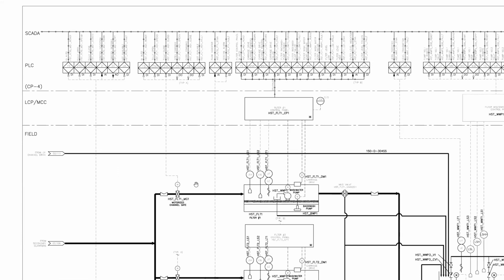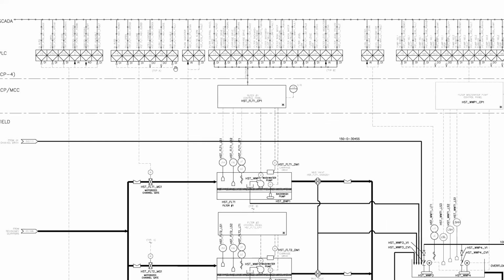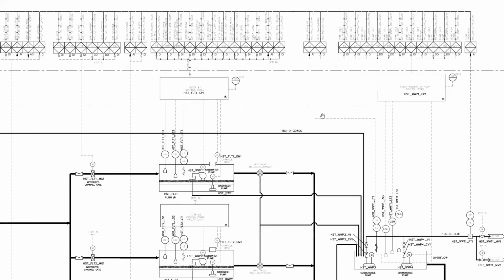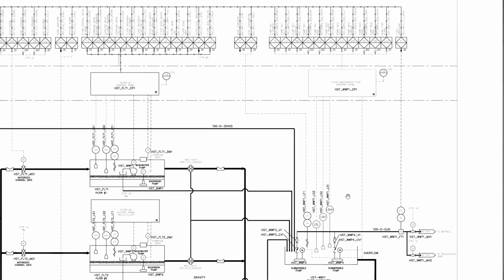So if you don't have IO drawings, or let's say you were given these drawings, but not panel drawings, you could start to build an IO list knowing, okay, well, I have a filter gate and this is the IO for that filter gate. And I have an existing PLC and I need to add that IO to that PLC. Well, this could help you build your required IO points. If you know how many IO points you need to add, then you can start looking at specifying cards. You can start looking at making guesses as to how long it's going to take you to develop new code. Well, I need to add 10 new pumps. Well, I think each one of these pumps will probably take me a day, so 10 days of labor. So starting using P&IDs is a great tool if you have them to be able to start getting IO counts and building the idea of your program and getting into pricing and part specking that way.